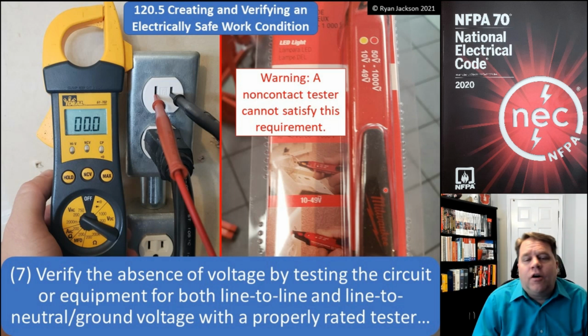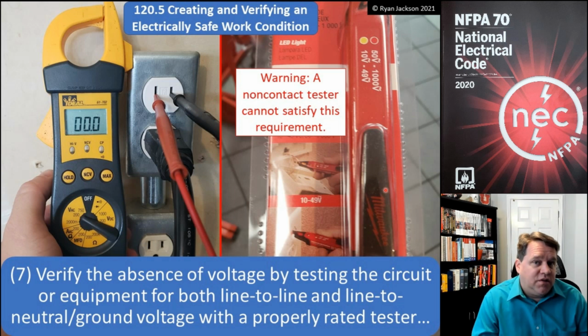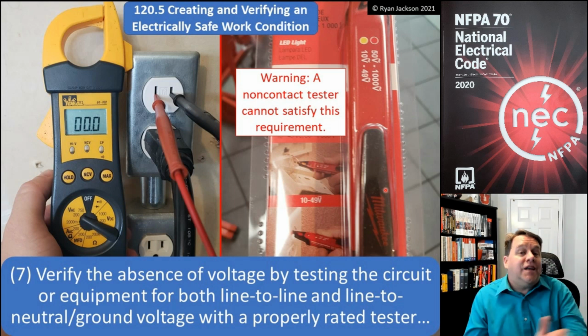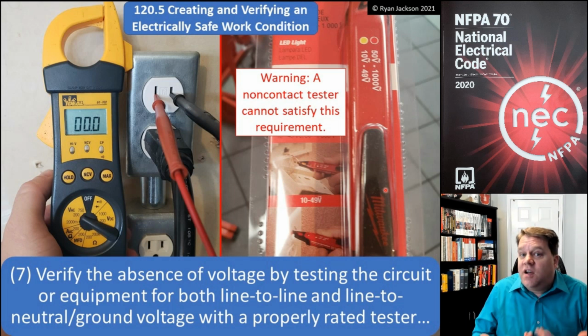All right. Once we have applied the lockout or the tagout device in accordance with industry standards, step 7 is we need to then verify the absence of voltage by testing the circuit or equipment for both line to line and line to neutral or ground voltage with a properly rated tester. All right, now I want to point out that at this point of the procedure, we are not yet in an electrically safe work condition. We're still creating the electrically safe work condition. So in other words, it's still on for all intents and purposes.